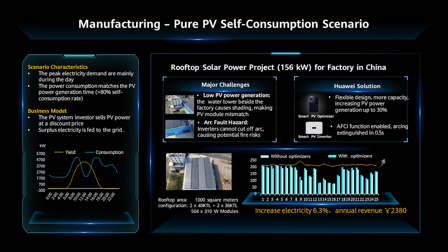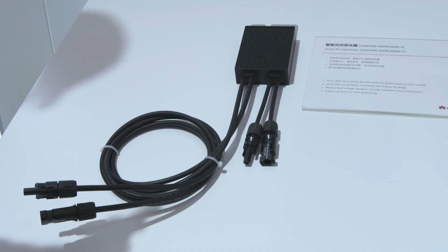Firstly, you can see the wall in the building next to the PV plant creates a shadow mismatch, which reduces the system power generation. And secondly, the traditional inverters cannot cut off the arcs, causing potential fire risks. So to address these two challenges, the owner replaced the 36 kilowatt inverter with a 40 kilowatt inverter, and the corresponding modules were fully equipped with Huawei Smart PV optimizers.